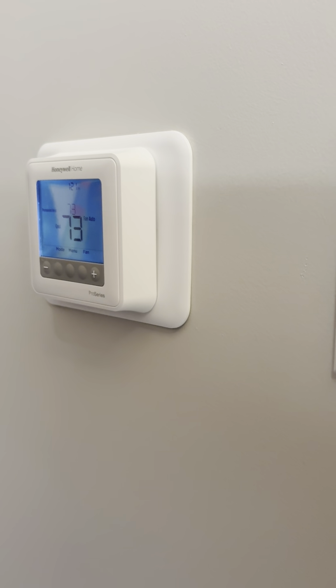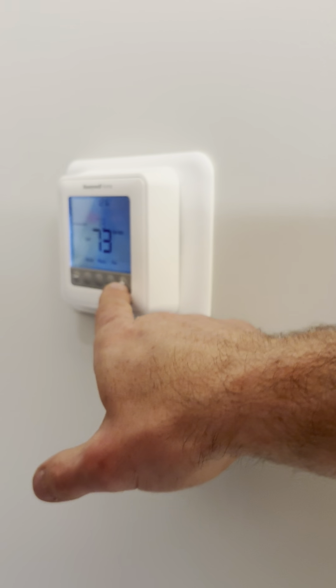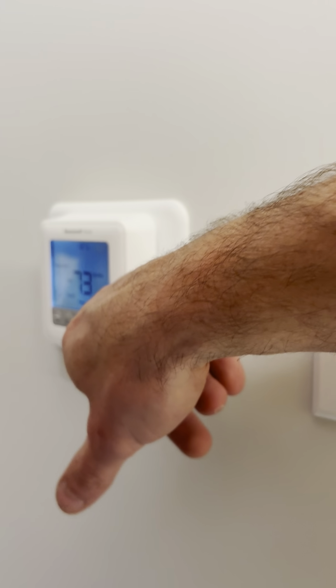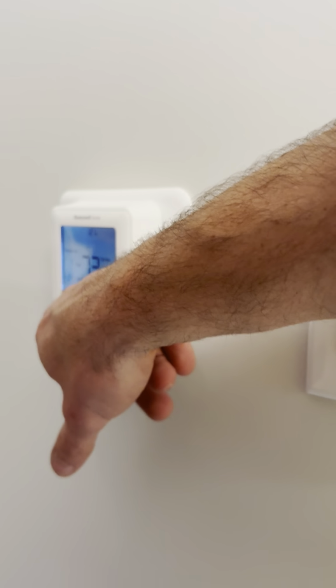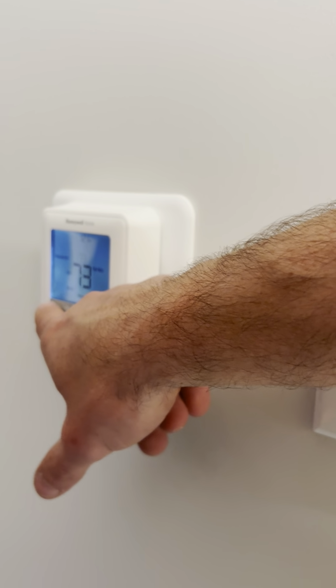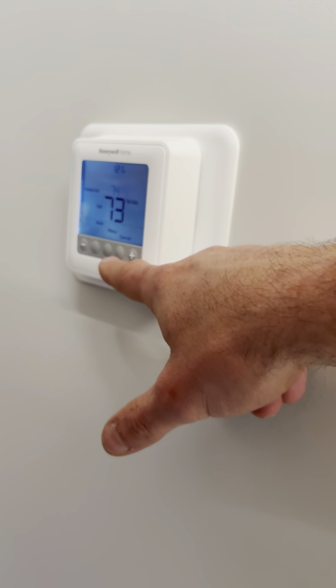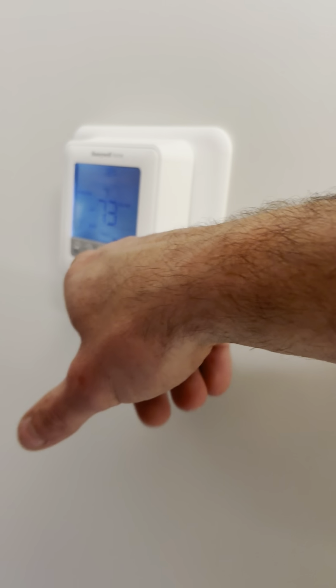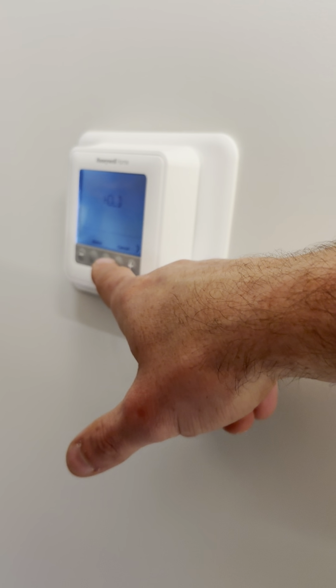These can be changed from Fahrenheit to Celsius too? Well, you just set your maximum set temperature. Right now the maximum set point non-programmed into it is 30 degrees - they can put it up to that for heat, and they can put it down to 11 degrees for cooling. You want to lock it so they only go 22 degrees max for heat, and 19 degrees for cooling.